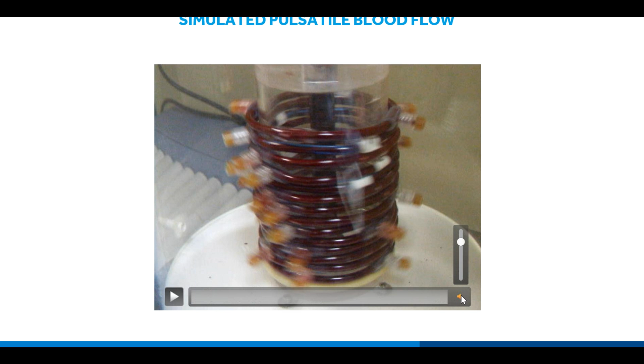We have another method that's called saline displacement. And I'm muting this so you guys don't have to hear us chatting in the lab. But this is a simple method where a syringe is hooked onto an epidural needle that sucks out a certain volume of the tube. And as it's sucking out volume, it's pulling in the same volume of blood. And so the test samples in the tube immediately get exposed to blood, and there's no air interface in this model. So test materials are immediately exposed to fresh human blood in these various models.